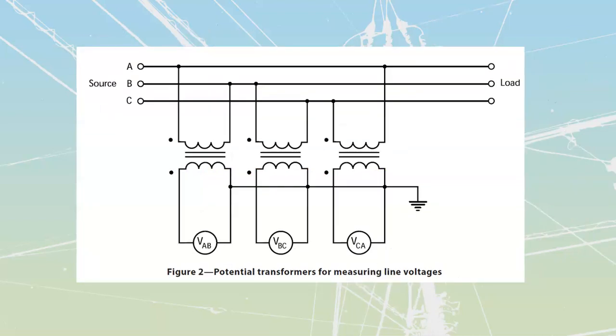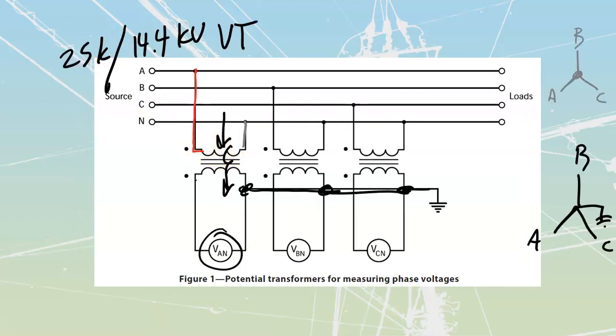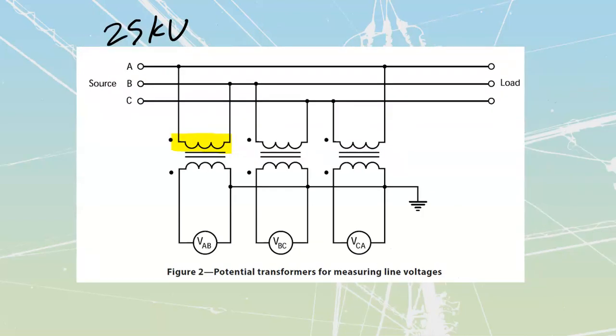Other times we're going to use our PTs when we have only line-to-line values of voltage. So if we have the same system, 25 kV, but now it is a delta type of system, I'm going to have 25,000 volts across here. I cannot use the same PTs as in the previous one, because in the previous one the voltage across the high side was 14.4. Now the voltage across the high side is going to be 25,000.